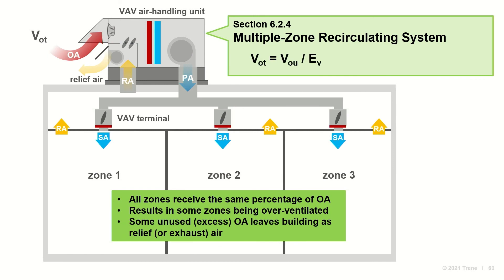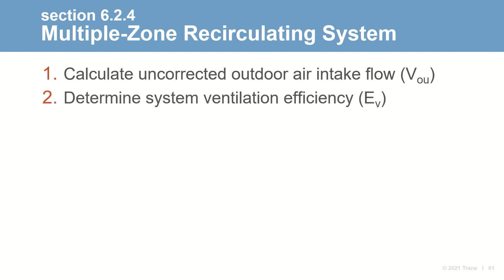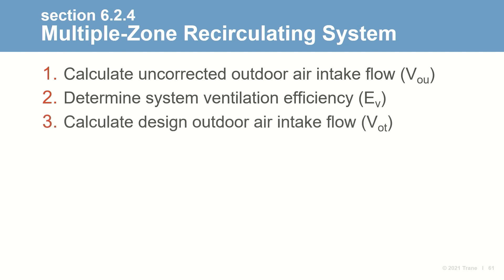To account for this, Standard 62 requires the designer to determine a System Ventilation Efficiency, E-sub-V, when calculating intake airflow for this type of system. There are three steps: first, calculate the uncorrected outdoor air intake flow V-sub-OU; second, determine the system ventilation efficiency; and third, calculate the design outdoor air intake flow V-sub-OT.